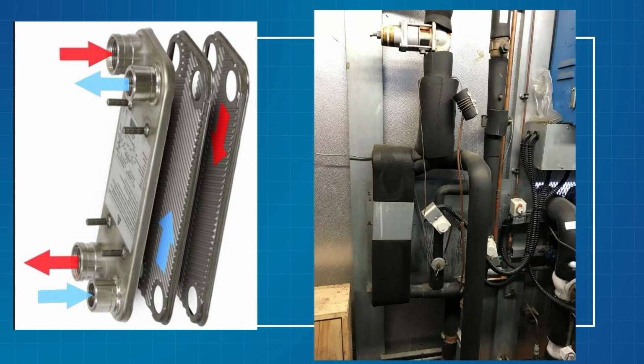We use this for CO2, we use this for steam, any time we're trying to transfer temperature between two different media, we can use a plate heat exchanger, okay? Super common. Nothing unique about this one at all, right? If we look at my blue side, the blue side is the side that's going to do the work. We call this the primary side. The blue side's the side doing the work. It's my primary side. It is an evaporator, right?